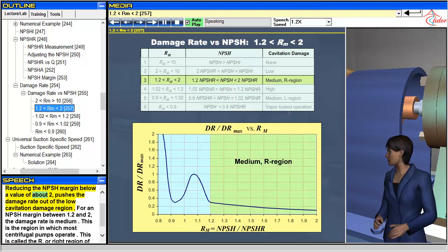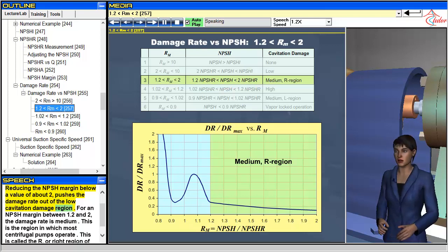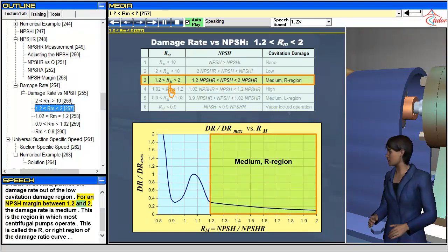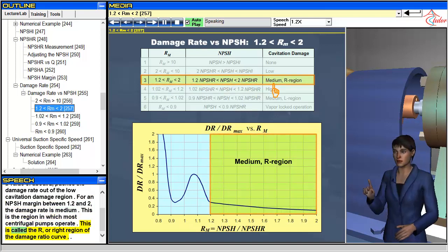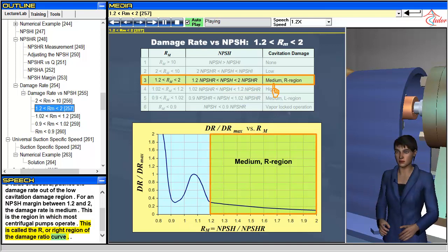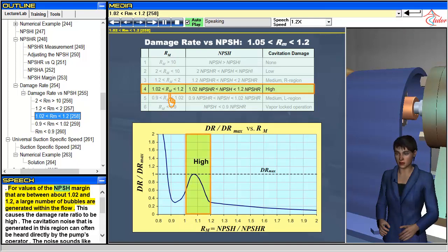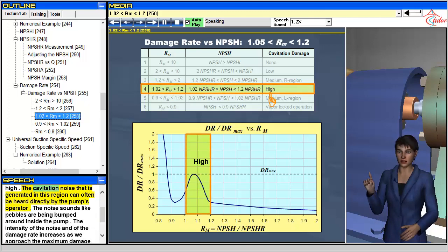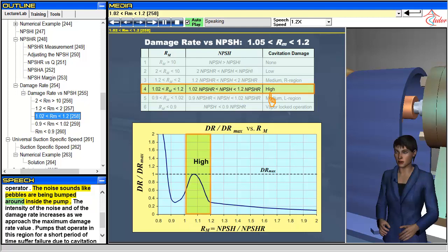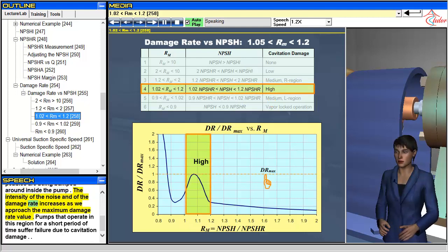Reducing the NPSH margin below a value of about 2 pushes the damage rate out of the low cavitation damage region. For an NPSH margin between 1.2 and 2, the damage rate is medium — this is the region in which most centrifugal pumps operate, called the R or right region of the damage ratio curve. For NPSH margin values between about 1.02 and 1.2, a large number of bubbles are generated, causing a high damage rate ratio. The cavitation noise in this region sounds like pebbles being bumped around inside the pump, and pumps operating here for a short period of time can suffer failure due to cavitation damage.